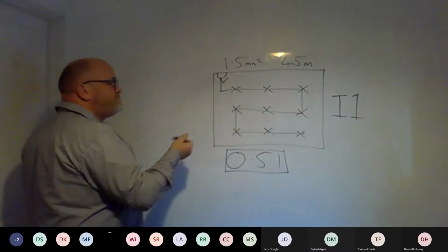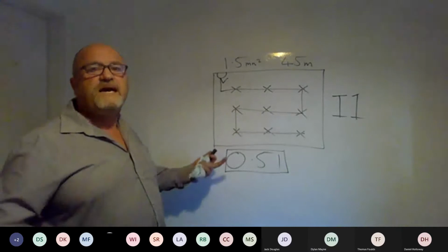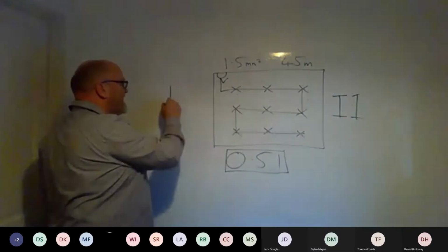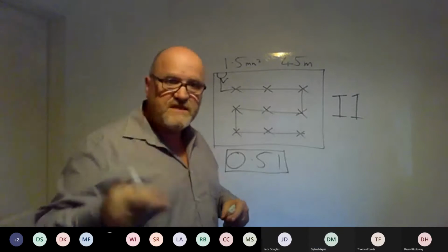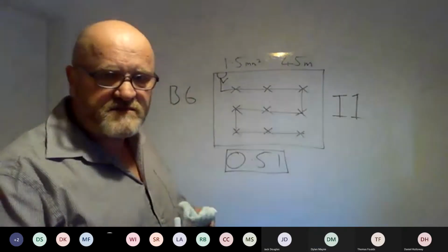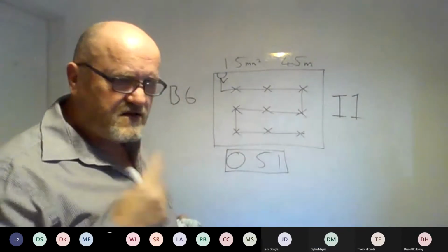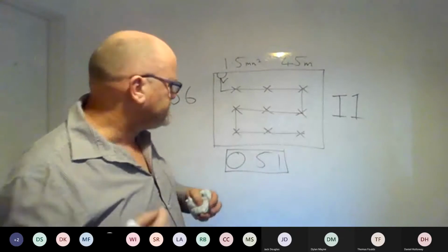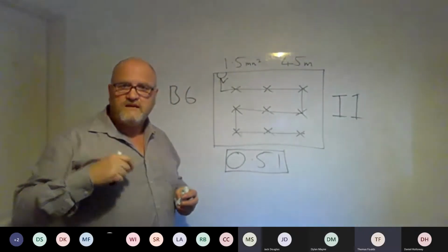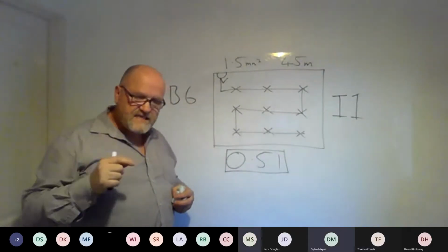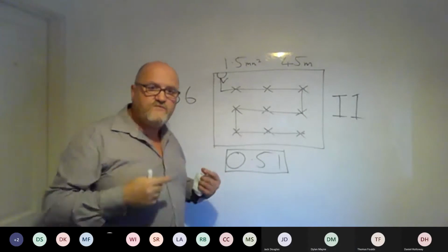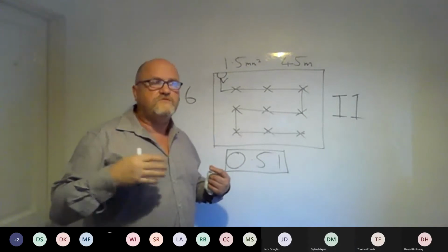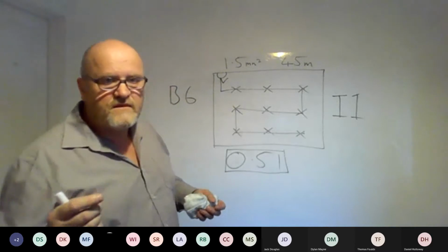And we have what's called the maximum impedance reading, and it's on table B6 of your on-site guide. It tells you what the maximum is. Can anybody tell me what the breaker is for a lighting circuit? What size do we use? B6. And for a B6 breaker, the most resistance you're allowed is 5.76 ohms.